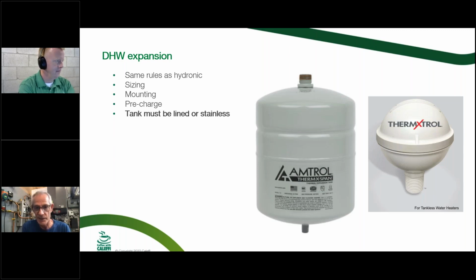It's going to be a lined tank. I think that tank has a stainless steel nipple on the top instead of a steel nipple, obviously. On the right there, that can be used for tankless water heaters that only hold a little bit of volume. Now, Cody and I talked about this yesterday. He said, you know what? Some of these new tankless water heaters have tanks in them now. I saw one brand has, I think, a 10 or 12 gallon tank inside the tankless water heater. Well, you've got to start paying attention to that, because now maybe that little softball on the side, that little domestic water expansion tank for tankless units, might not have the capacity to do that.